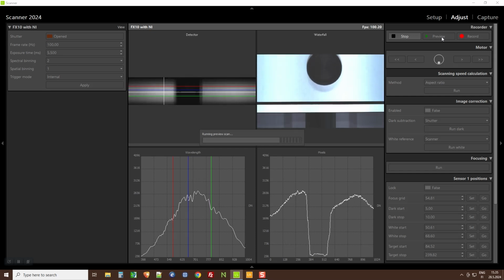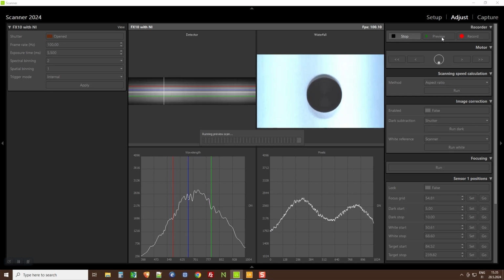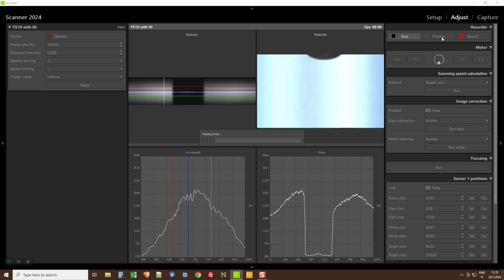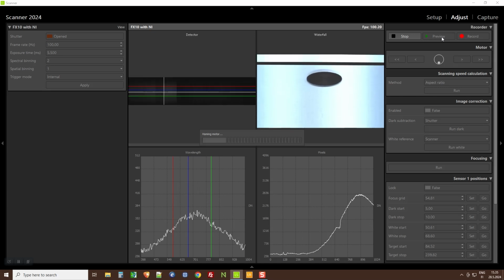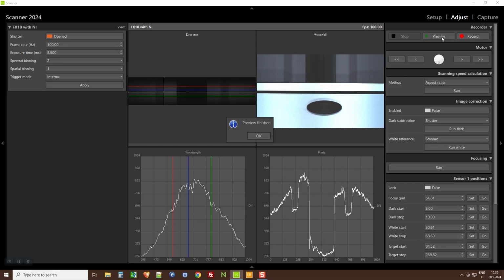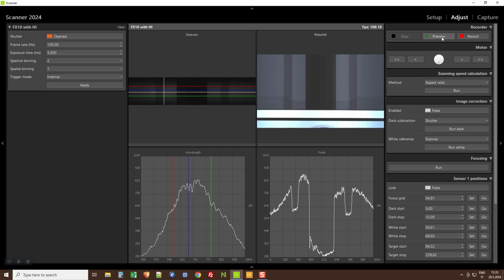And now we have a round which is looking round. Okay. Now we can take it back with us, and we are almost ready to make the data acquisition. Notice that when you want to make a really good data acquisition, we recommend to have the white reference located exactly at the same level as the sample. Like this you get really better absolute reflectance values.